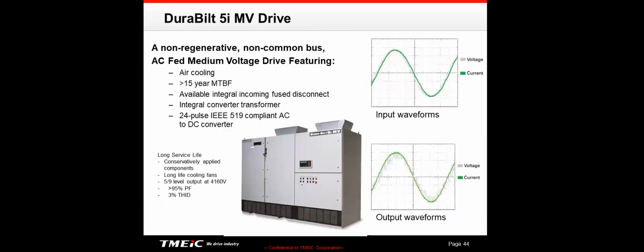This is the DuraBilt 5i. Now that is a multi-pulse type of drive. This particular drive is a 24 pulse. In my opinion, I would like to see 24 pulse on minimum on everything. 12 pulse is certainly much better than 6 pulse, and 18 pulse is getting pretty good, but I think in a medium voltage drive domain, you really deserve at least a 24 pulse drive.